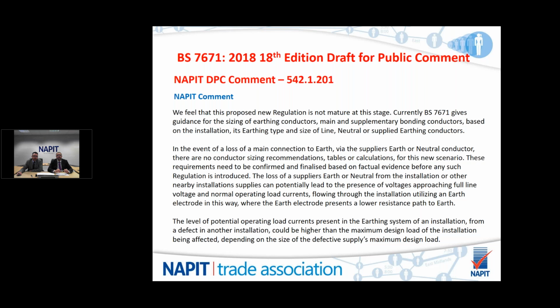This is a problem. In the event of a loss of a supplier's earth or neutral from an installation or other nearby installation, it can be affected or it can affect the installation that has an electrode fitted in this way. If that electrode presents a lower resistance path to earth, the level of potential operating load currents present in this earthing system of an installation from a defect in another installation could be way higher than the maximum design load of the installation being affected. It could be getting close to the defective supplier's maximum design. It could come through or be channeled through your earthing system. We don't feel that's acceptable. We don't feel the cabling or the earth electrodes, bonding conductors, etc., have been thought about. So we don't feel that at this particular time this is a mature regulation to put in.